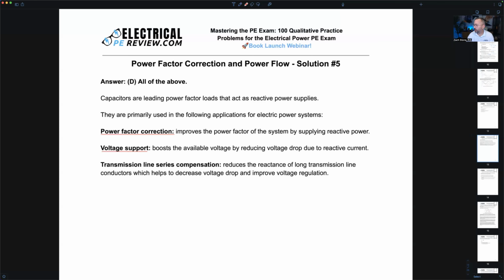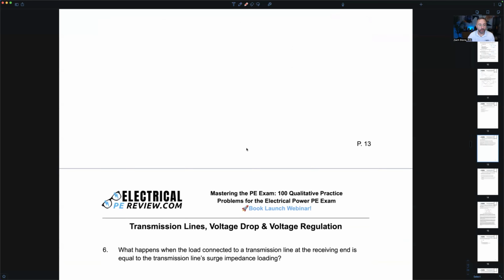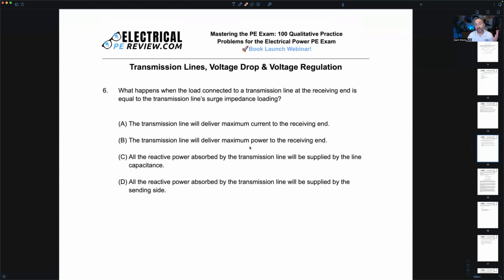Let's take a look at number 6. So again, I'm going to read the question out loud, and I'll read the answer choices. Give me the answer you think it is in the chat. What happens when the load connected to a transmission line at the receiving end is equal to the transmission line's surge impedance loading? Good vocabulary word there, surge impedance loading, SIL for short. Do we think it's A, the transmission line will deliver maximum current to the receiving end? B, the transmission line will deliver maximum power to the receiving end? C, all the reactive power absorbed by the transmission line will be supplied by the capacitance? Or D, all the reactive power absorbed by the transmission line will be supplied by the sending side? A, B, C, or D?